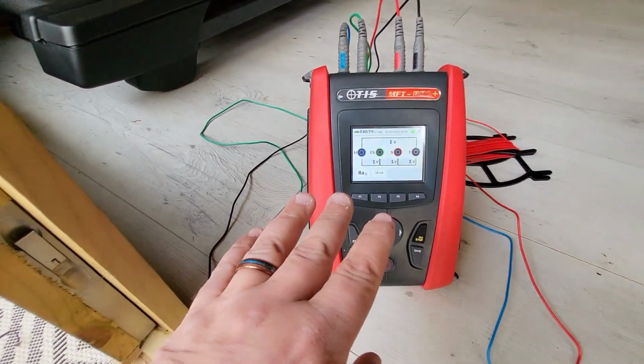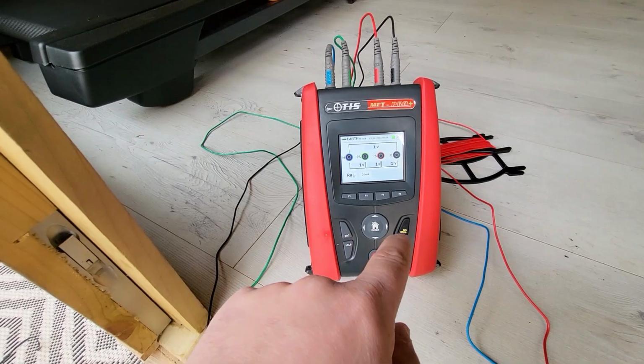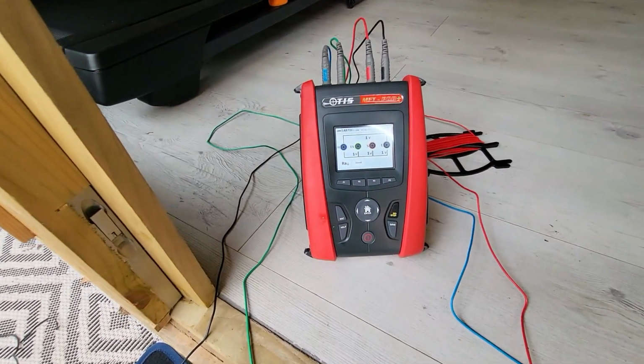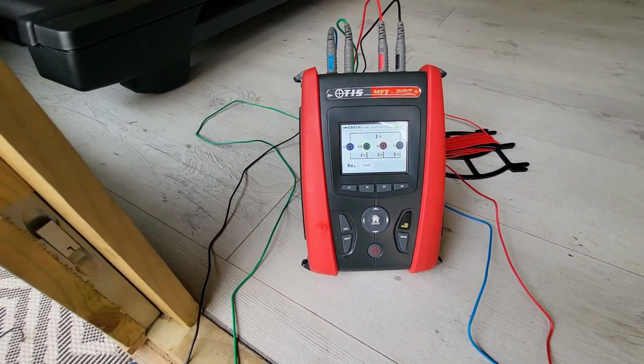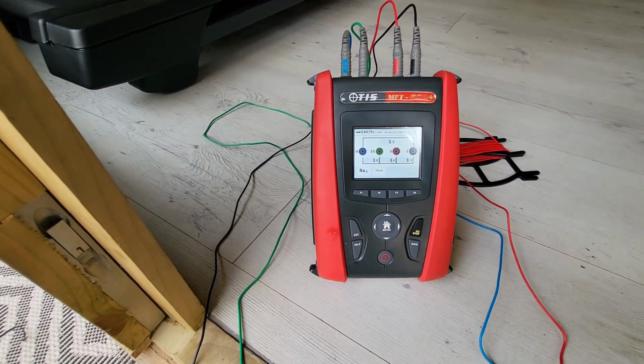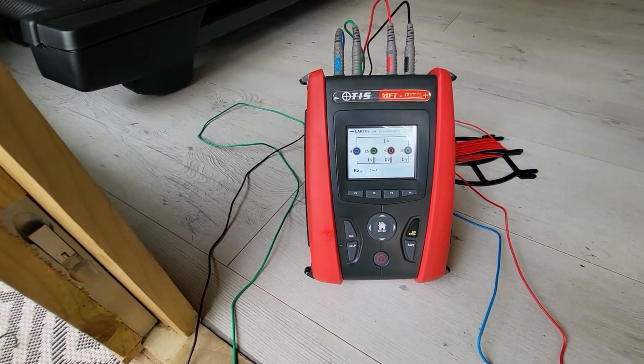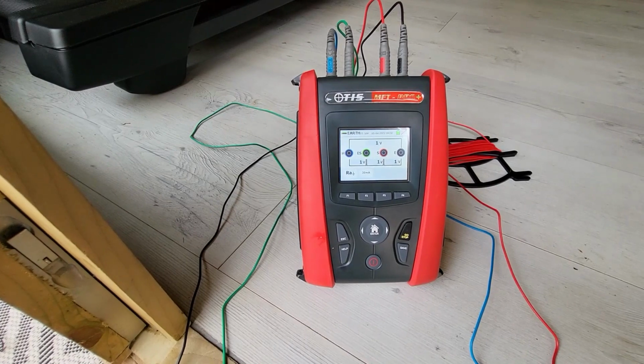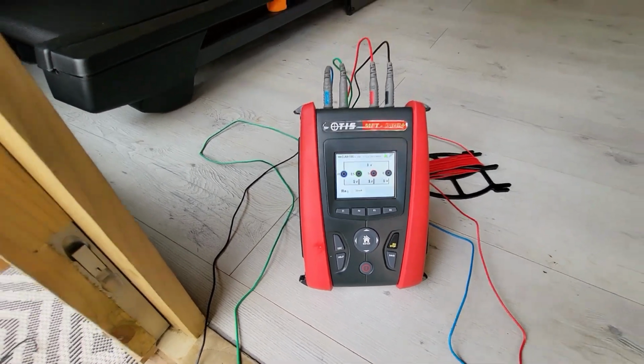There is a specific way of setting this up to do your resistance measurements between the main earthing terminal to a house, for example, and an earth electrode, to see if you've got any overlaps where they might be crossing over in the mass of earth. So when you think you've got a detached earth electrode, you actually don't - you're still connected essentially through the mass of earth itself and buried services within it.